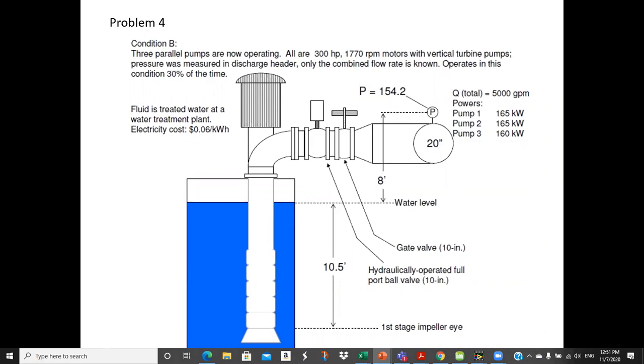And then we have another condition here, condition B. We're at 5,000 GPM, and we have a higher power, obviously, on the pump. And also, well, not obviously, but in condition 2, we're going to operate 3 of these pumps in parallel, and they're all the same pump. So 3 in parallel, all 300 horsepower. So we're running 900 horsepower worth of pumps, 1770 RPM motors, and they go into a distribution header, and this is where we're measuring the pressure in that header. And it operates in this condition 30% of the time.